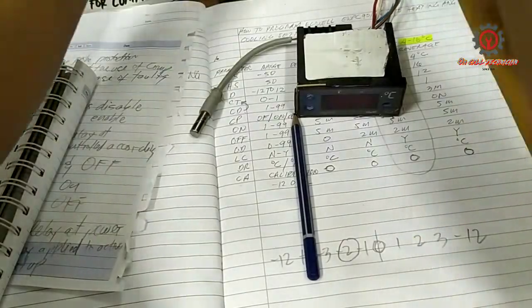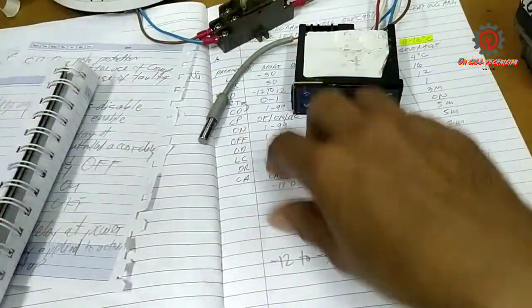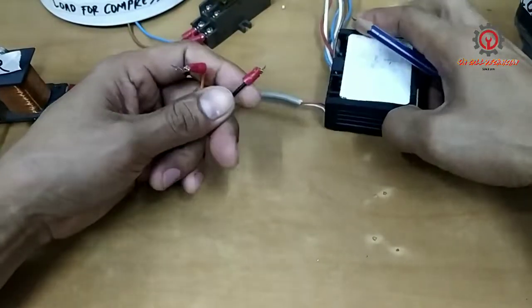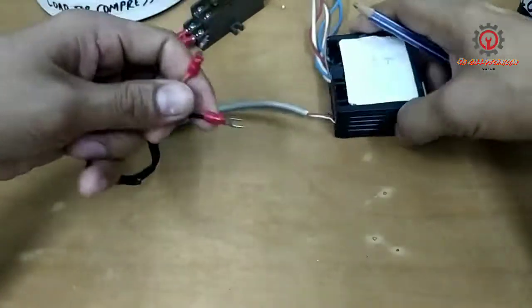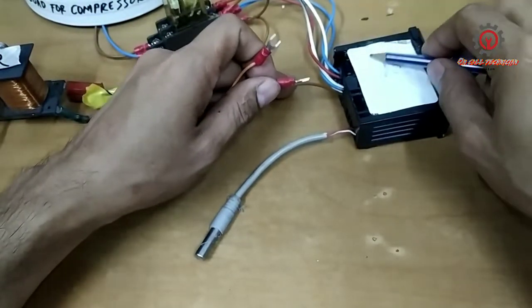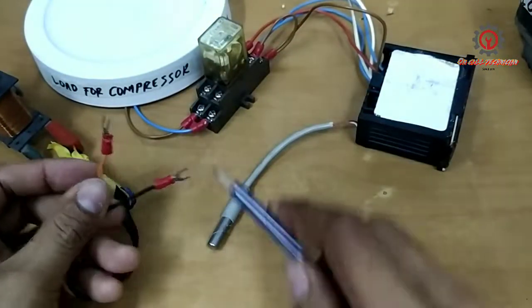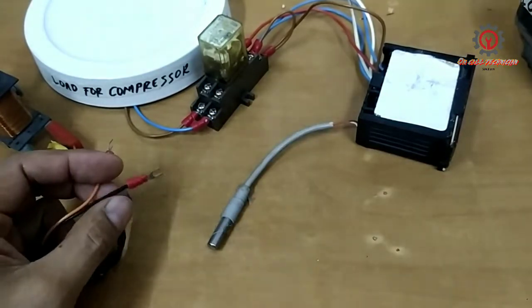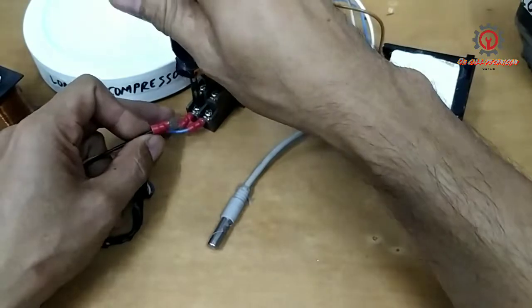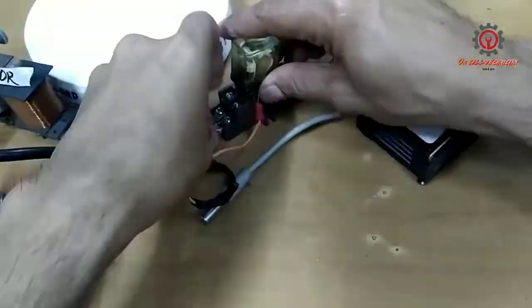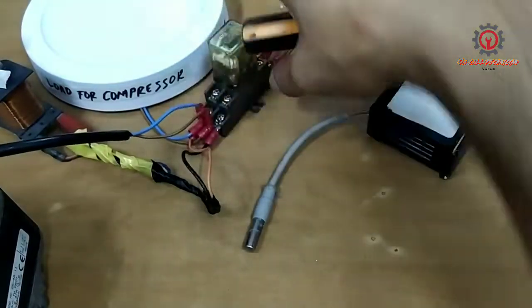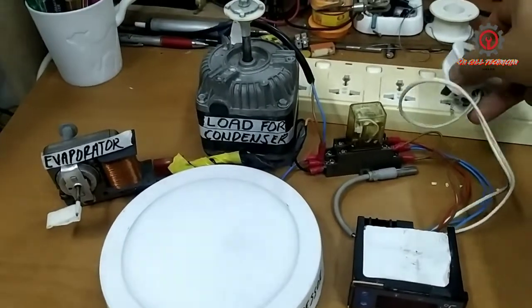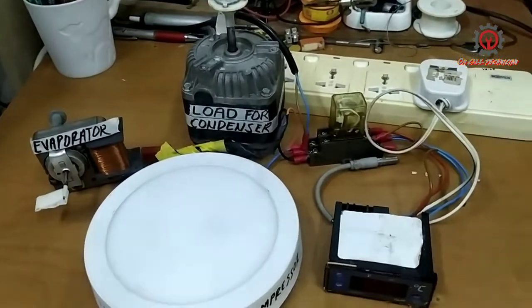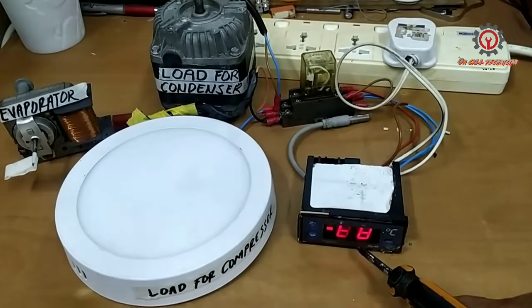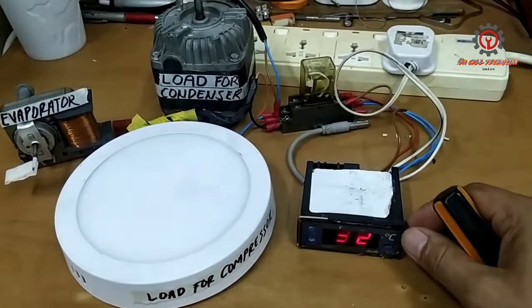Okay, last but not least, guys, we're going to install the load. Usually evaporator controllers have different parameters, but since this is only one relay, we're going to put this to this output voltage of this relay. Okay, guys, the power is on, and let's see if the 1 minute delay is being counted now.